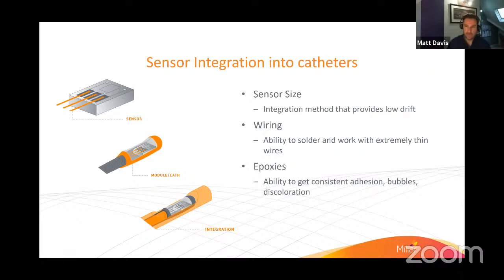This is an extremely important part of the process. This seal is directly related to drift and sensitivity, and it's important to get consistent adhesion and eliminate bubbles. If the seal is too thick, the catheter would have reduced sensitivity, and we wouldn't see those beautiful signals that Keith is getting in his blood pressure. If the seal is too thin, the catheter would have increased sensitivity, but it would have a short lifespan in liquid—maybe minutes to hours instead of longer term. Finding the right balance is key, and this comes from experience.